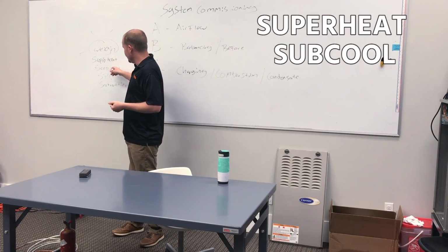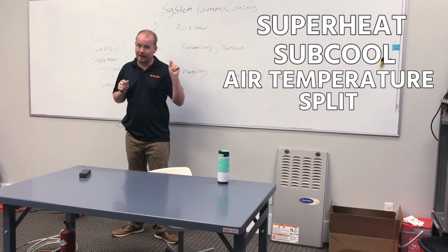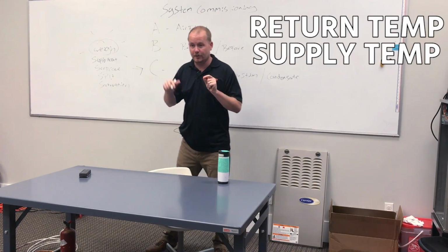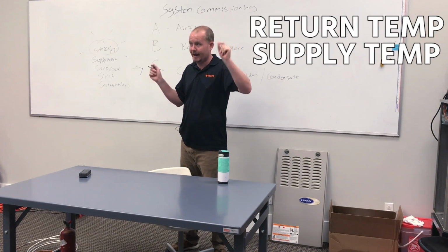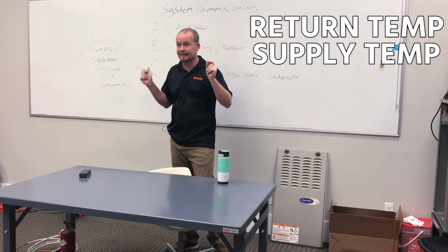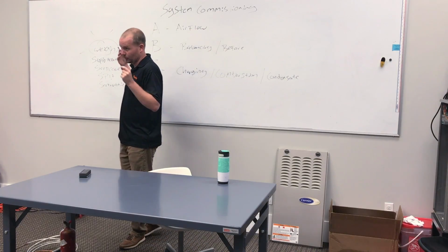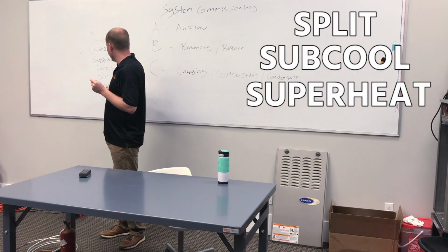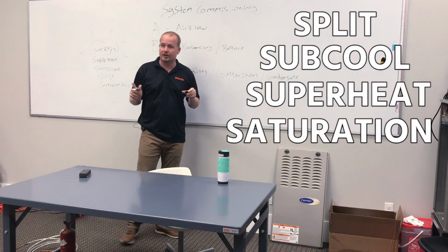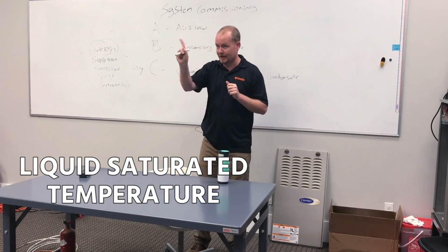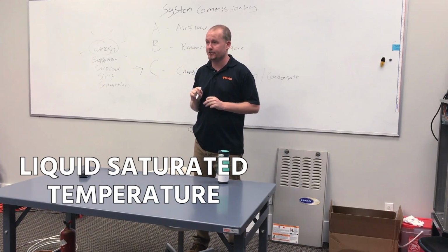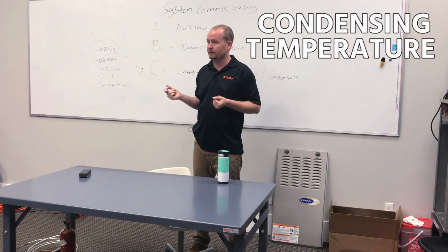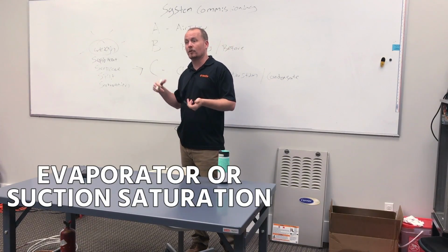Then you're going to check superheat, subcool, and air temperature split, which I think we're not doing as much as we should. Return temperature, supply temperature, check that regularly, because it tells you a decent amount about airflow especially. Split, subcool, superheat, and then saturation. And saturation is just what is my liquid saturated temperature, the temperature on the gauge, otherwise known as condensing temperature, and what is my evaporator or suction saturation.